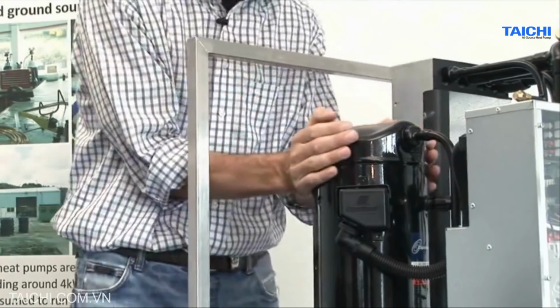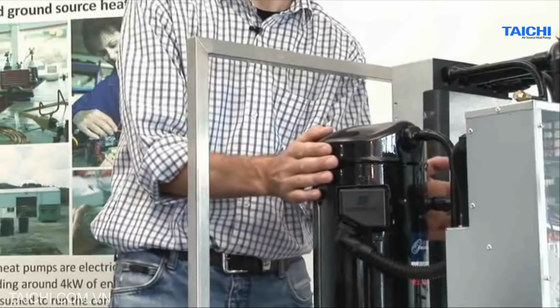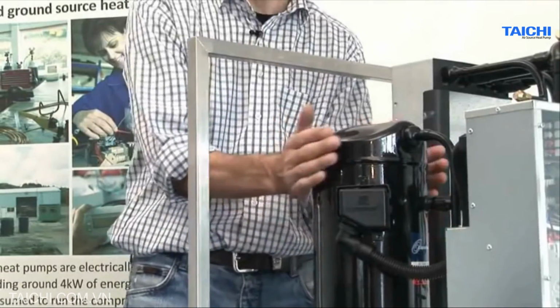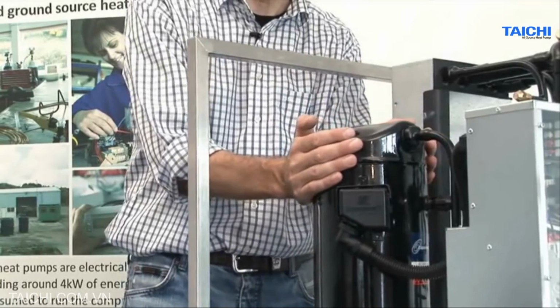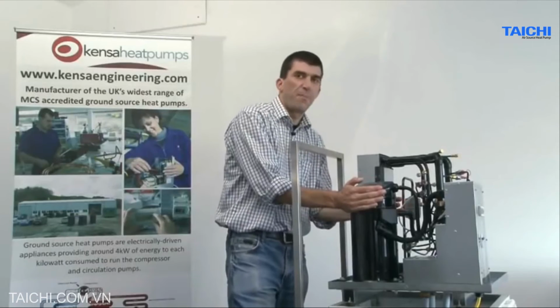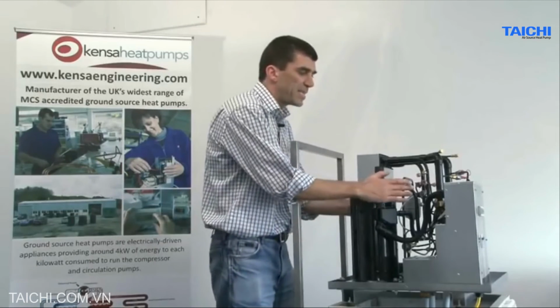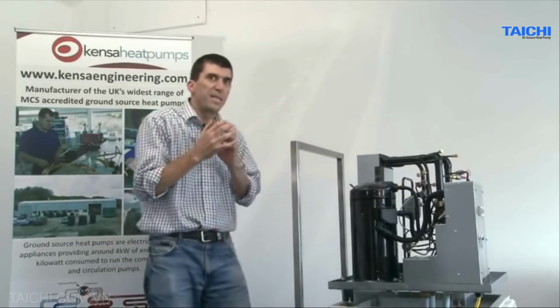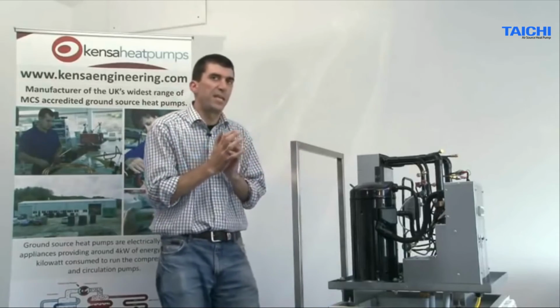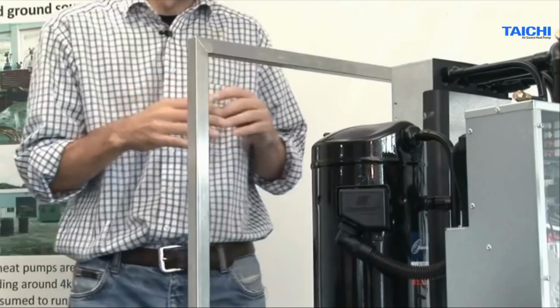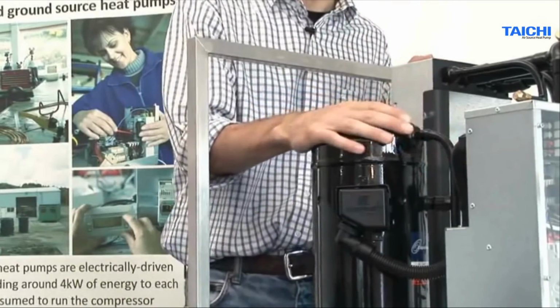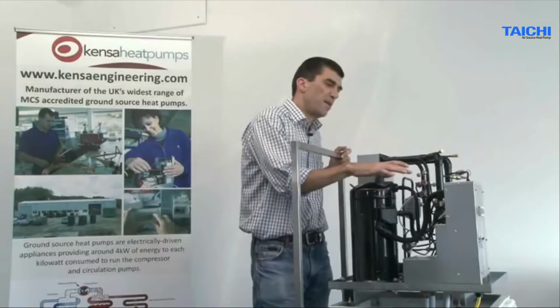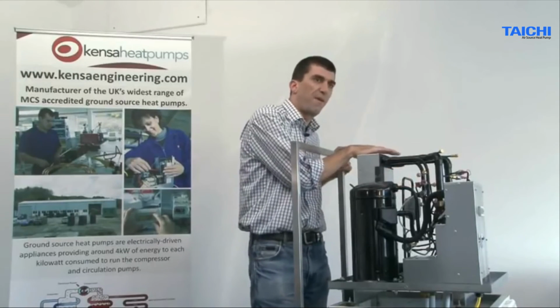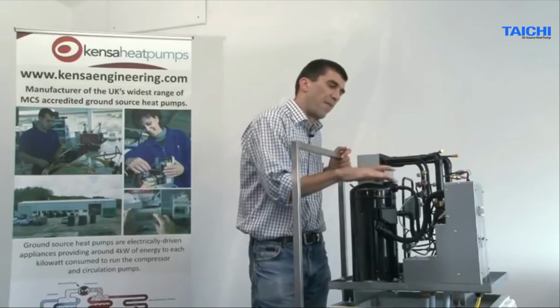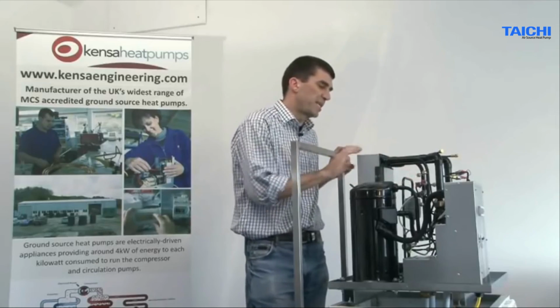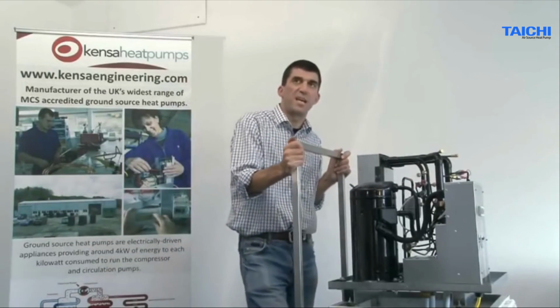Well, it's exactly the same with the way the compressor handles the gas. The gas is probably 10 or 15 degrees C after it's passed over the motor. It enters the scroll set, the suction part of the compressor, and gets squeezed down, probably entering at about 50 psi in old money and exiting at about 250 psi. And that effect of that squeeze raises the temperature. It hasn't created the energy, it's purely concentrated, it's squeezed it. And that's why the discharge pipe from the compressor is probably up around 60 or 70 degrees Celsius. Most of that heat energy that's in there has come from the evaporation in the ground side heat exchanger. And that, of course, is where we started the story. That gas passes back into the condenser and off we go again, about every 45 seconds on a typical installation.